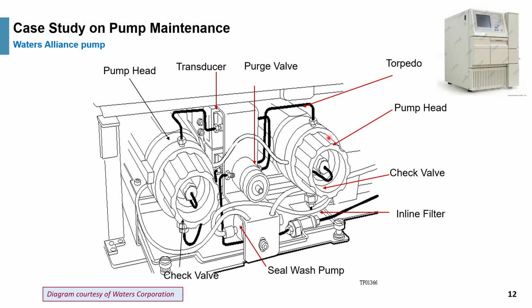So here are the two pump heads. Most pumps are dual piston in series, so each pump would have two pistons in the pump. This actually turned out to be a quaternary pump, right? So there are two pump heads in here. Here's the pump head, and here are the check valves. You can change the check valves; they are highly accessible.